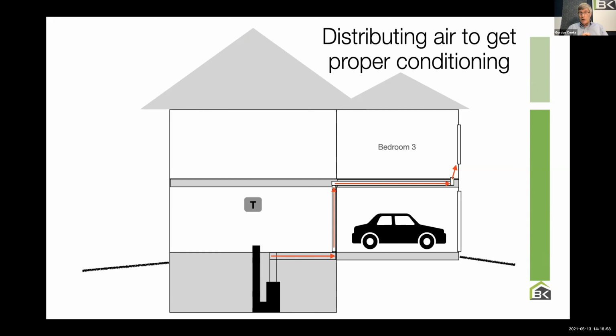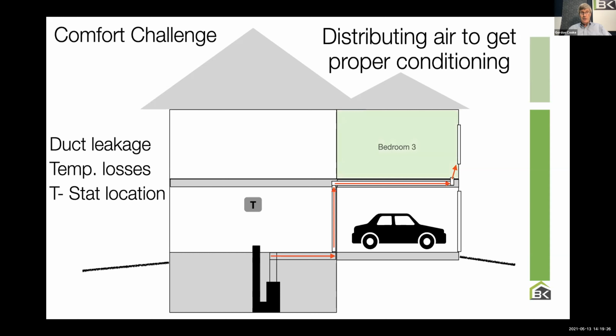And there's that bedroom number 3, right? Remember bedroom number 3? Look where the thermostat is. The thermostat is seeing a kitchen and a fridge and a whole bunch of kids and TVs. It's hardly seeing any outside walls. And bedroom number 3, meanwhile, is seeing a cold floor, a cold ceiling, 2 cold walls, and a big cold window. And in the summertime, it's seeing hot elements as well. So imagine that comfort challenge because of those elements, and then superimpose on that potential duct leakage, the temperature loss of that duct as it goes through the garage, and the thermostat location makes this room really, there, I'm out of sync.